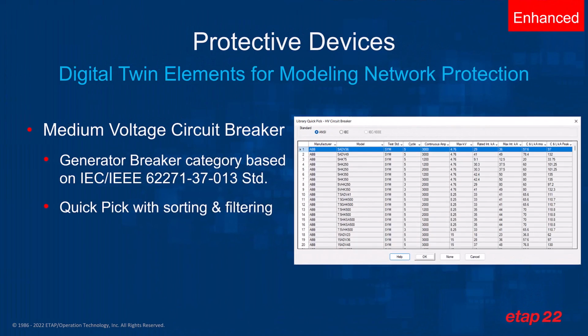ETAP 22 also includes digital twin elements for modeling network protection. One of the changes done for modeling the network protection is improvements to the high voltage or medium voltage circuit breaker library. The library now complies with IEC/IEEE 62271, which is the standard for high voltage switchgear and controlgear for alternating current generator circuit breakers.